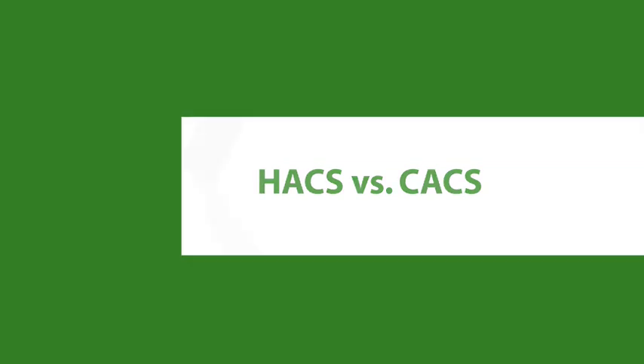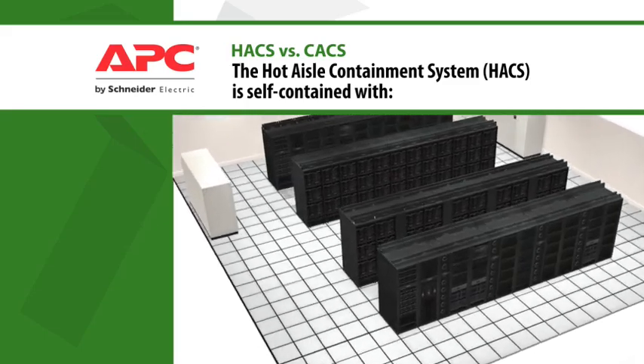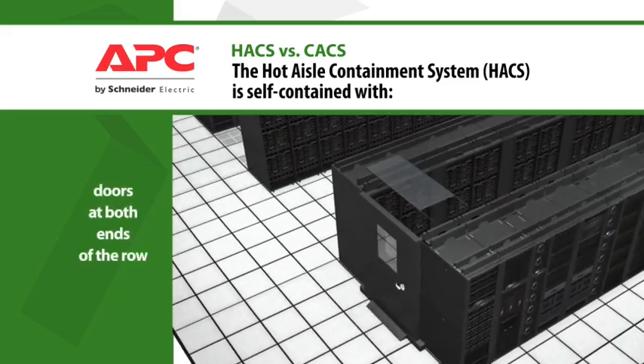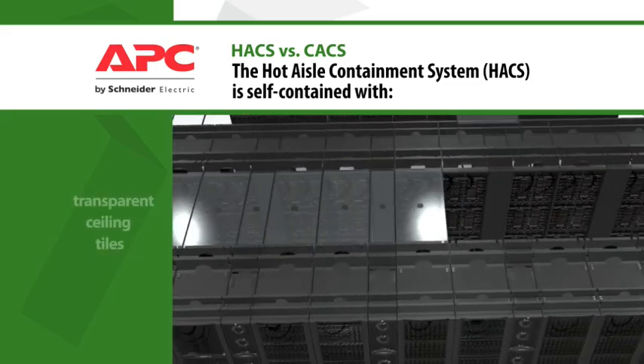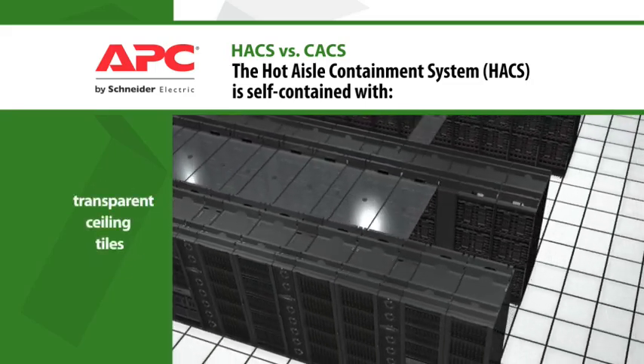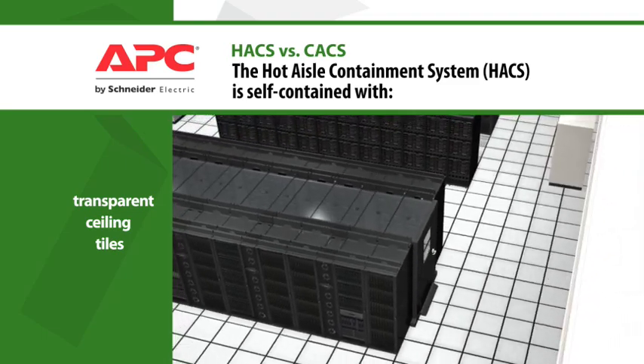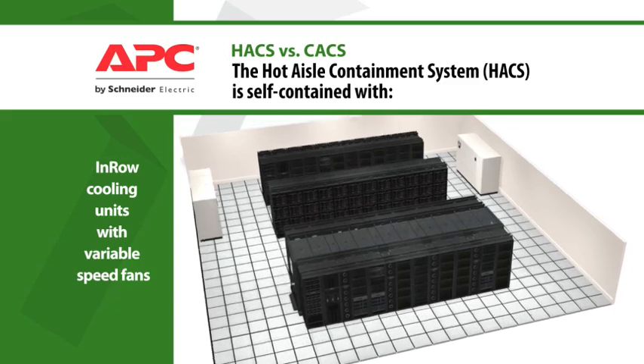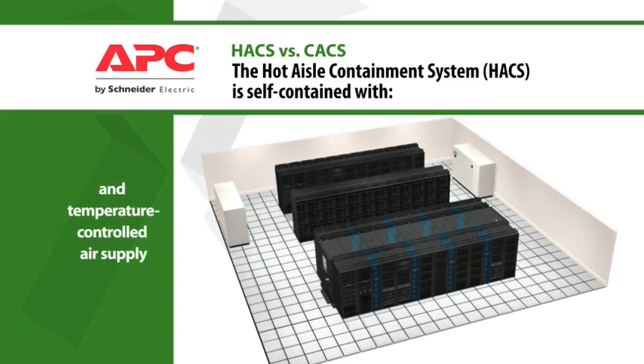APC's Hot Aisle Containment System, or HACS, consists of doors that cap both ends of the row, transparent ceiling tiles, and APC's own in-row cooling units with variable speed fans, and a temperature-controlled air supply to the cold aisle.